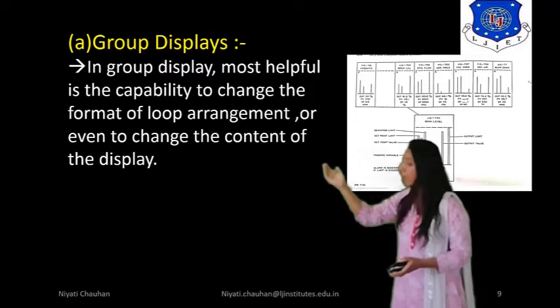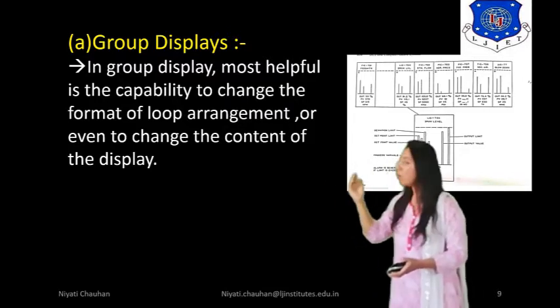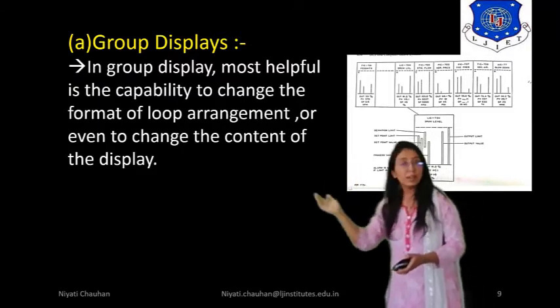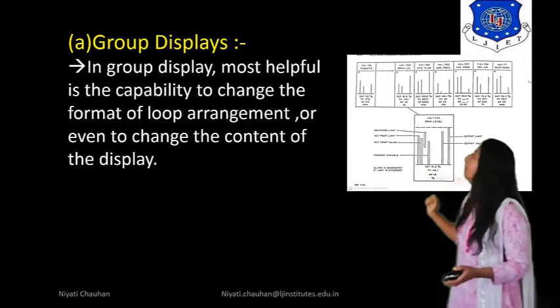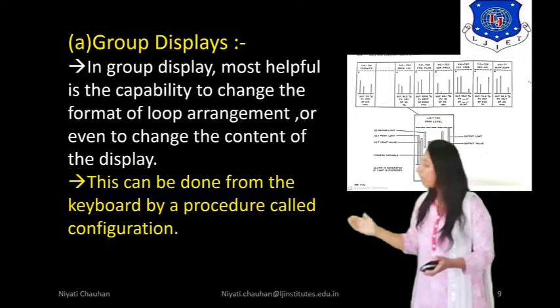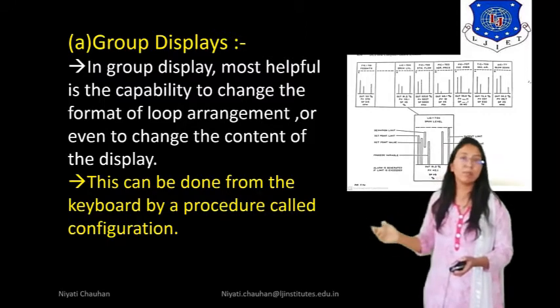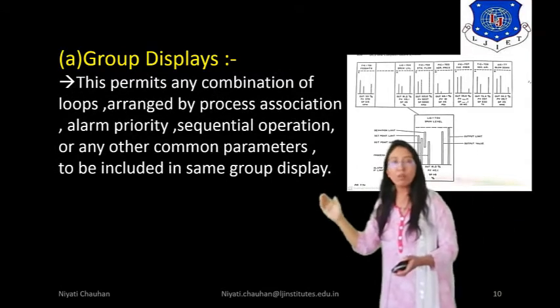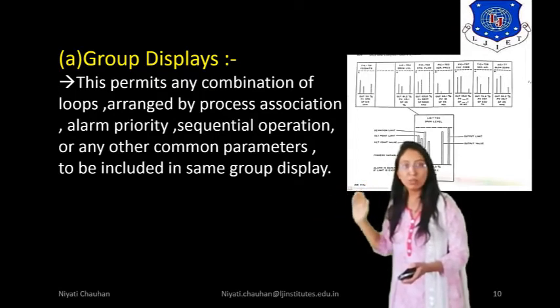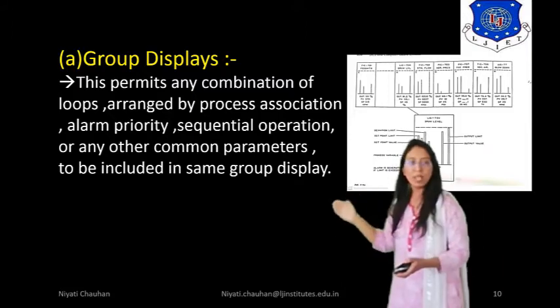In the group display, the most helpful feature is the capability to change the format of loop arrangement or even to change the content of the display. This can be done from the keyboard by a procedure called configuration. This permits any combination of loops arranged by process association, alarm priority, sequential operation, or any other common parameters to be included in the same group display.